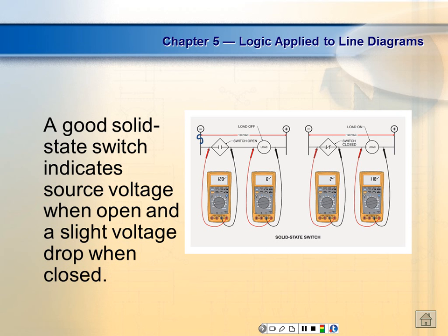So if I had a fuse right there, and then we came over and we had our black lead right here, or one of our leads right there. If I check it right there, I should have 120 volts or 24 volts. If I move it right here, I have 120 volts, then that fuse is good because it's dropping no voltage, right? So I got 120 volts on one side, 120 volts on the other side. How much is dropped? None. So that's why we had to check that. We had to put the batteries in the box and turn it on, and we'd check on this side of the fuse. If we had 0 volts on this side of the fuse and 12 volts on the other, the fuse was bad. And that's why you can do it in your car, by the way.